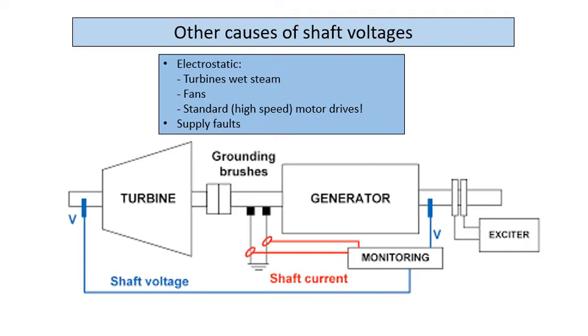So you put insulated bearings in, insulated couplings, insulated bearing pedestals, if you can't, and then you put earth brushes in to divert. So even if you've got insulated bearings, you put an earth brush in to divert what current might go through the bearing, away from it. Because even if you don't have breakdown of your oil film in a bearing, you can still have degradation of the grease or the oil due to currents. So especially on VSDs where the frequency is high.